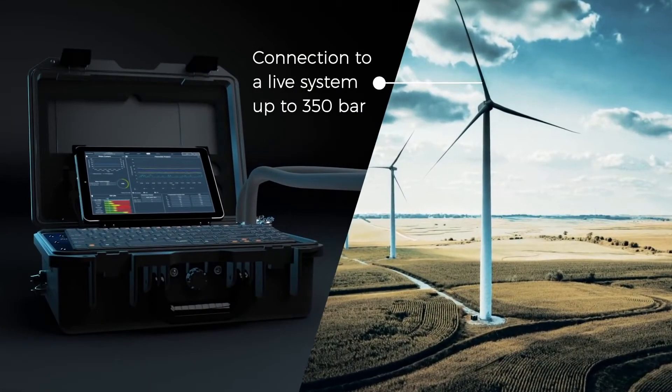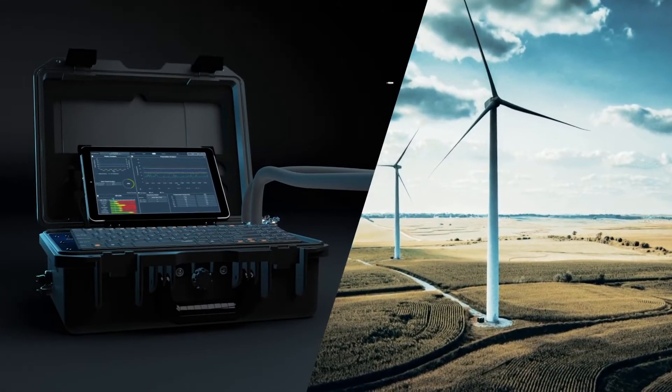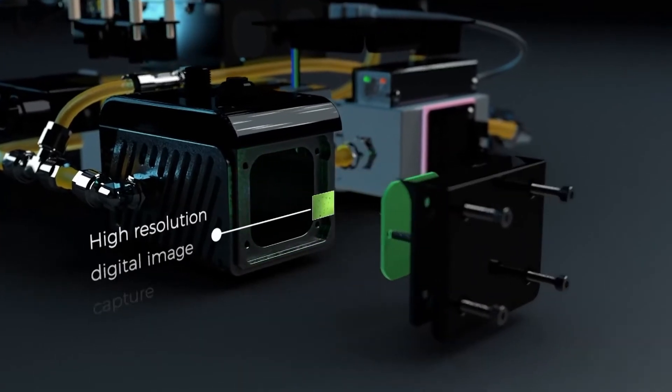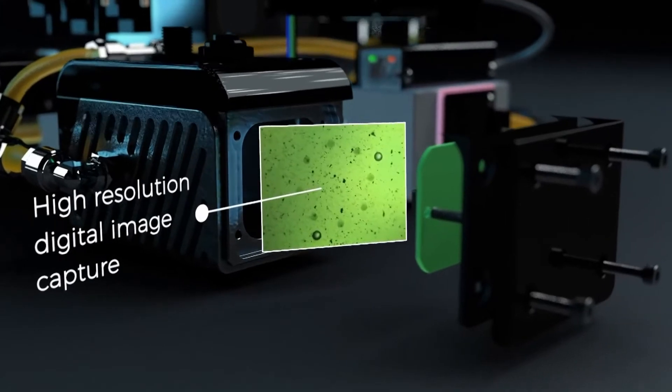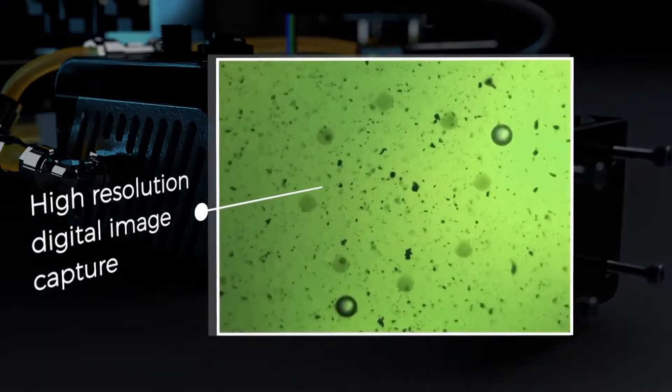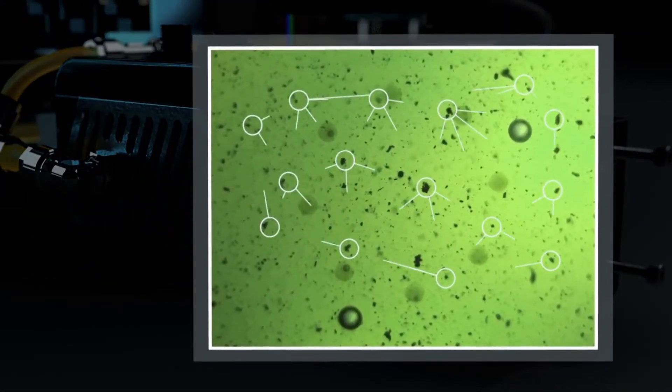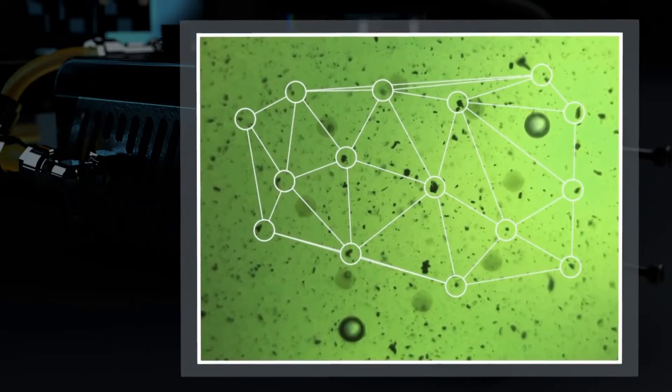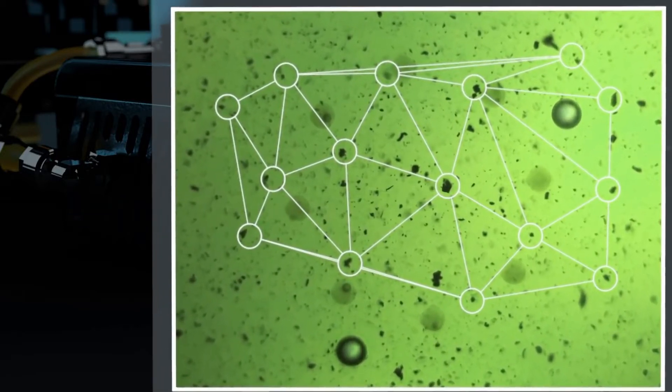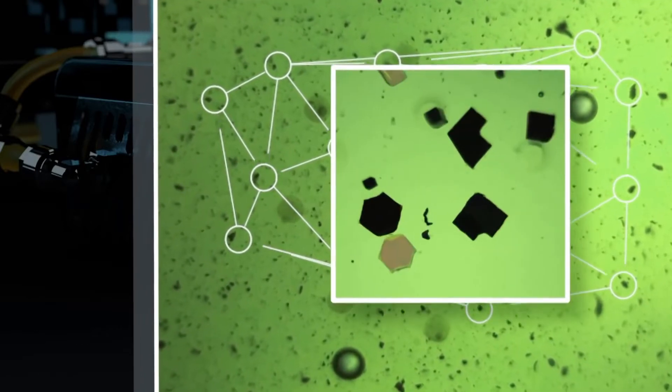The digital imaging particle counter uses high-resolution color image capture combined with advanced algorithms to sort particles into fatigue wear, cutting wear, sliding wear, and fiber identification, giving root cause analysis and ISO counts. Specific particles can be measured and analyzed in detail.